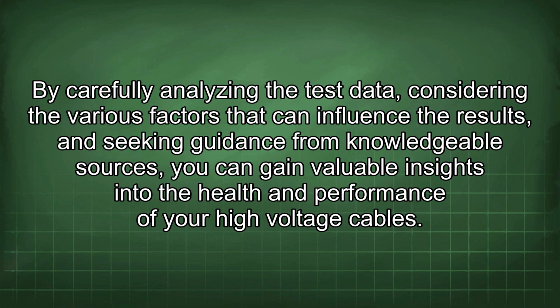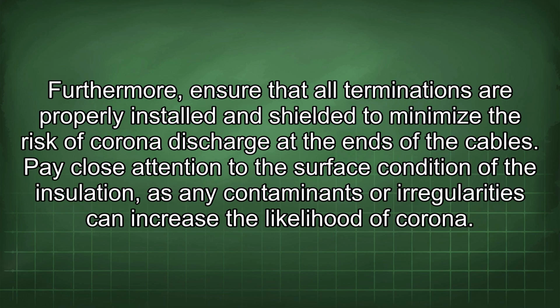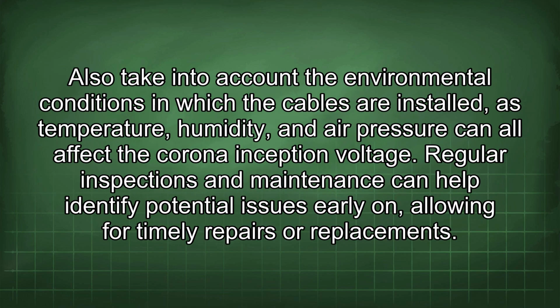By carefully analyzing the test data, considering the various factors that can influence the results, and seeking guidance from knowledgeable sources, you can gain valuable insights into the health and performance of your high-voltage cables. Furthermore, ensure that all terminations are properly installed and shielded to minimize the risk of corona discharge at the ends of the cables. Pay close attention to the surface condition of the insulation, as any contaminants or irregularities can increase the likelihood of corona. Also take into account the environmental conditions in which the cables are installed, as temperature, humidity, and air pressure can all affect the corona inception voltage.